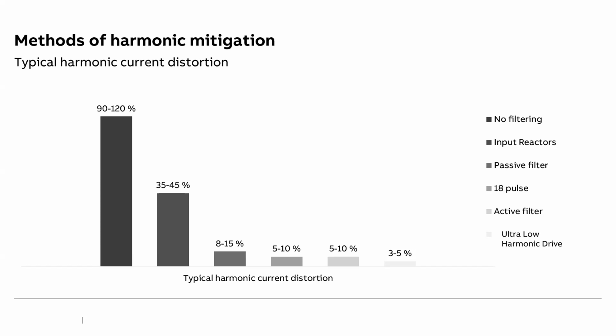Then there are certain disadvantages, like a passive filter causes a deterioration of power quality. The power factor drops drastically, and in many places you have to consider additional power factor correction devices also. Passive filters mostly function at the full load value because they have a fixed impedance value and are designed for a particular load condition, which is mostly the full load condition. So when the output reduces or the speed reduces, if it is a VFD application, then obviously the load will reduce.